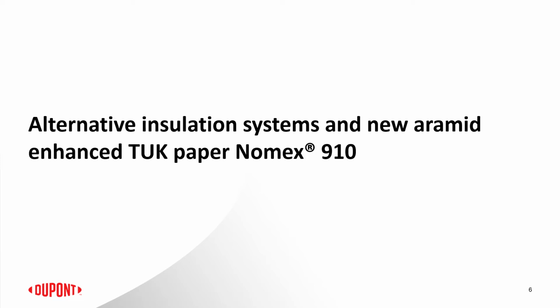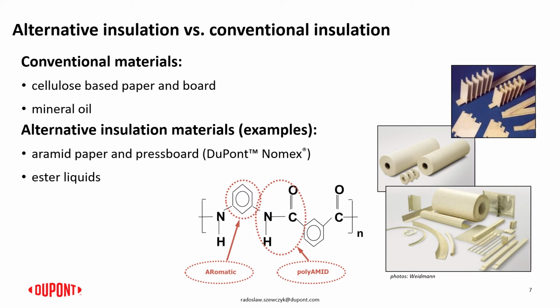So when talking about alternative insulation systems, we can talk about the conventional insulation systems and the high temperature insulation systems. The conventional materials traditionally used in the transformers include the cellulose-based paper and board immersed in mineral oil, while the alternative insulation systems may include Aramid paper and pressboard. In this case, we could talk about DuPont Nomex, and they may be often combined with the ester liquids, whether synthetic or natural ester liquids. Out of Aramid paper and pressboard, all or the majority of the typical insulation components can be made, whether based on paper or pressboard, for satisfying the insulation needs in the distribution or power transformers.